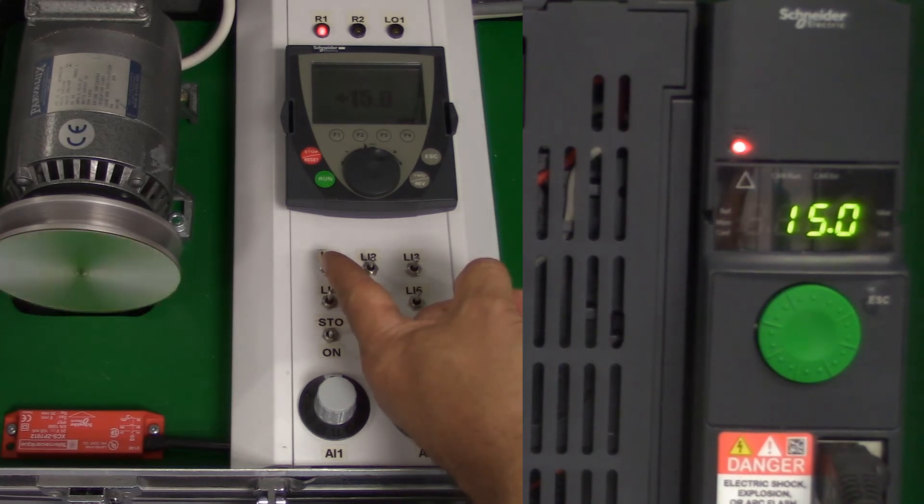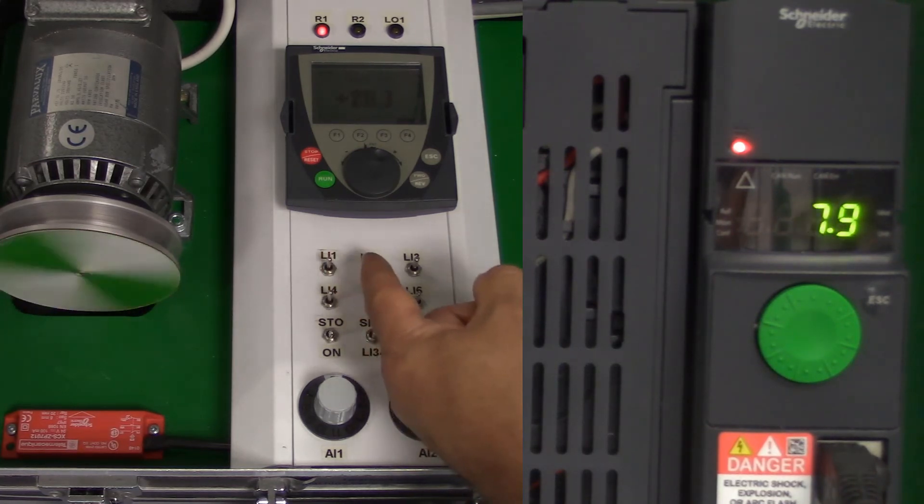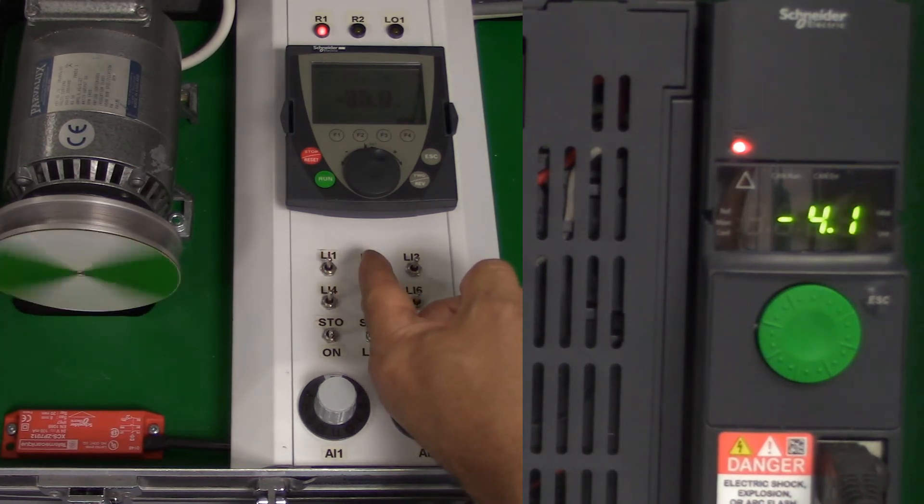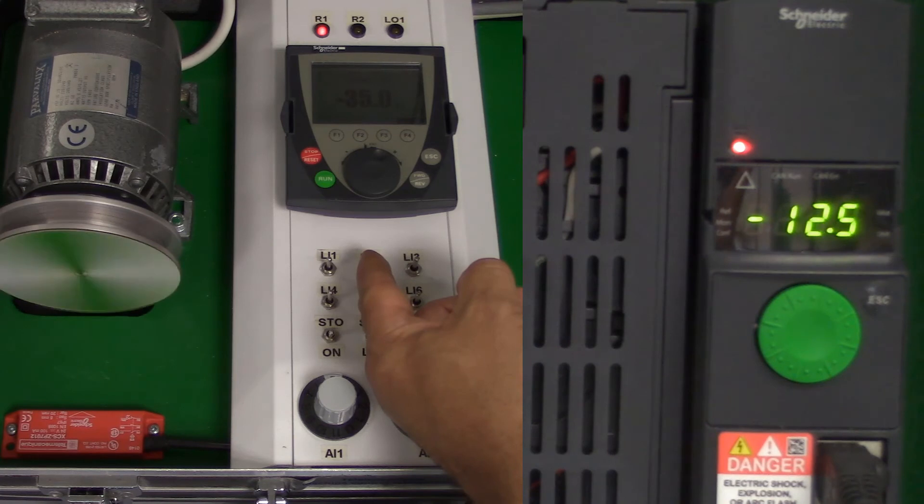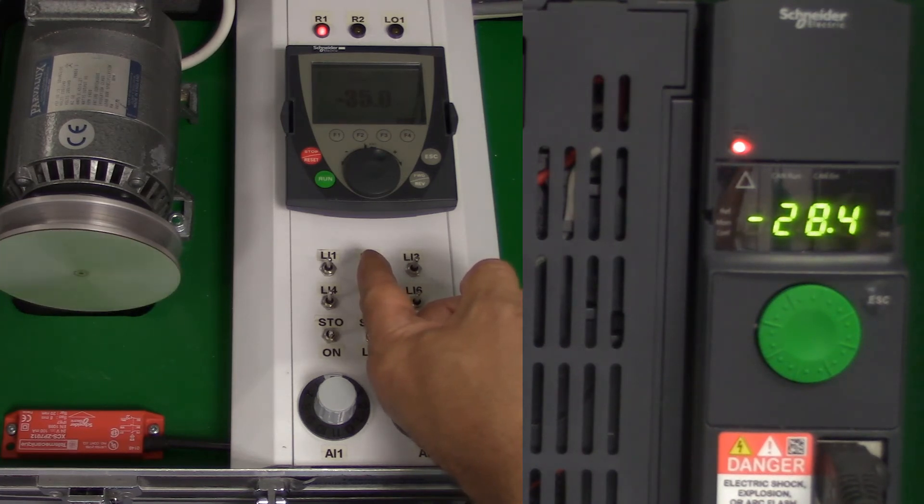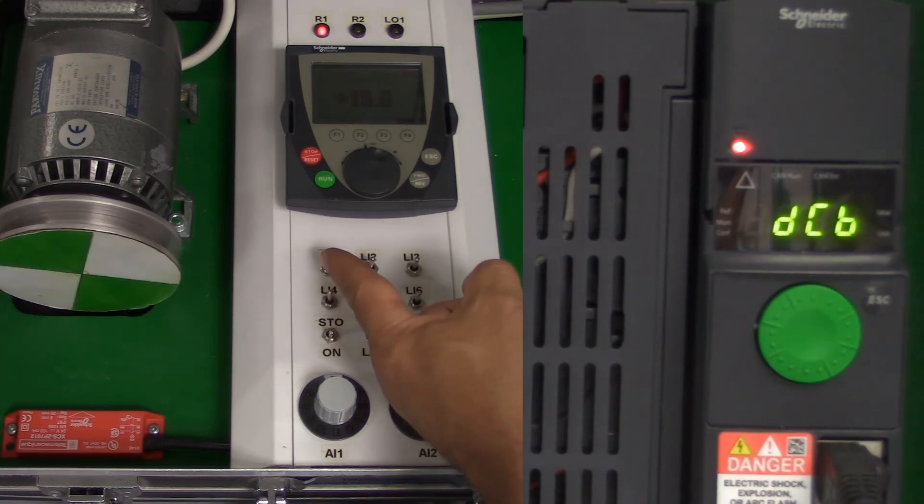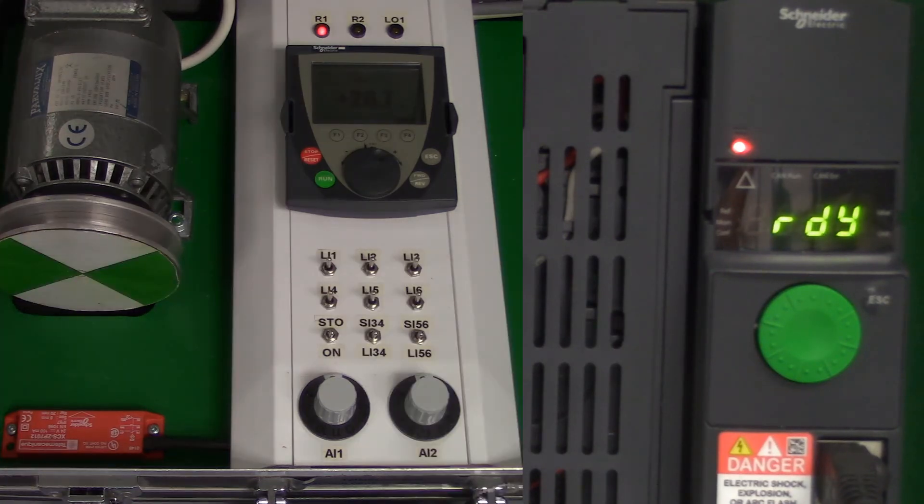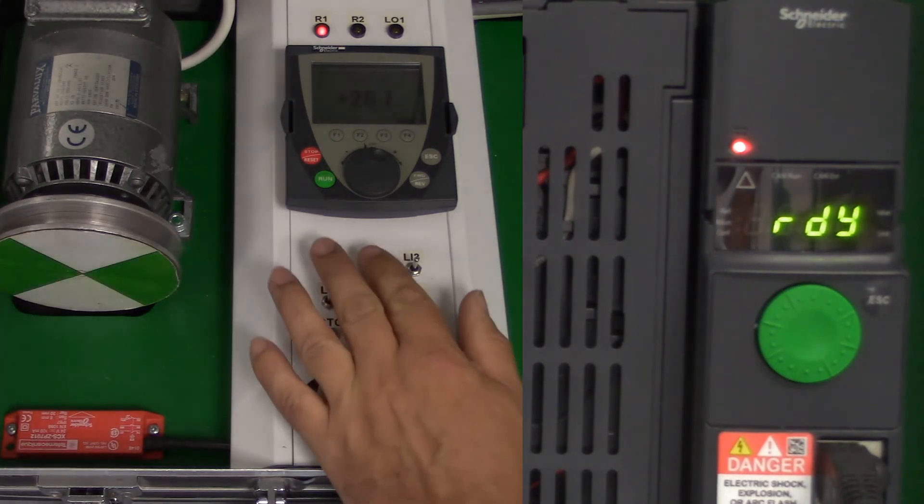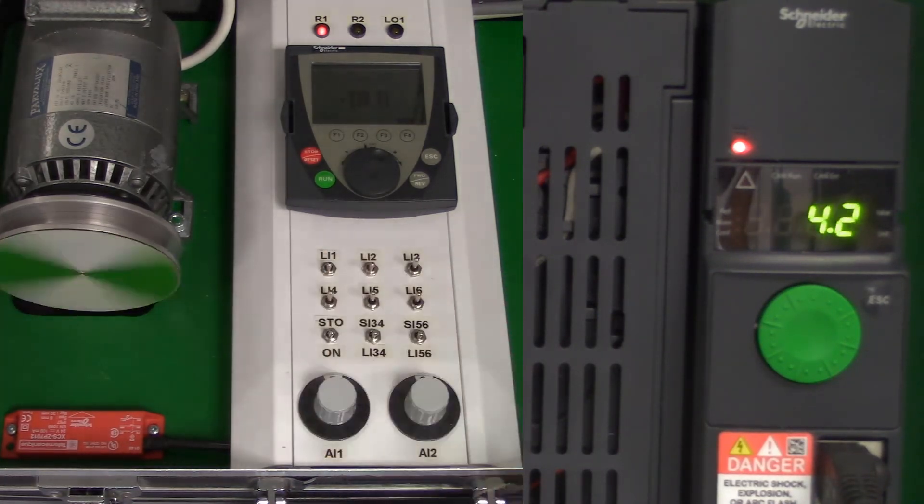You will see ramp down between the two though. These ramp down times and ramp up times can be independently adjusted, or you could have a freewheel stop, or you could actually set two different ramp times for forward and reverse.